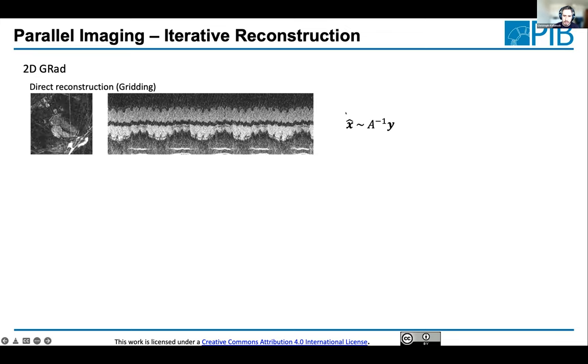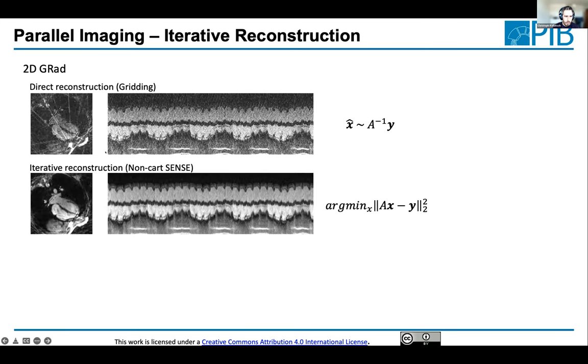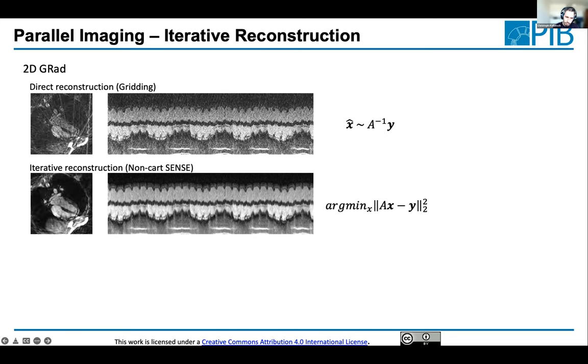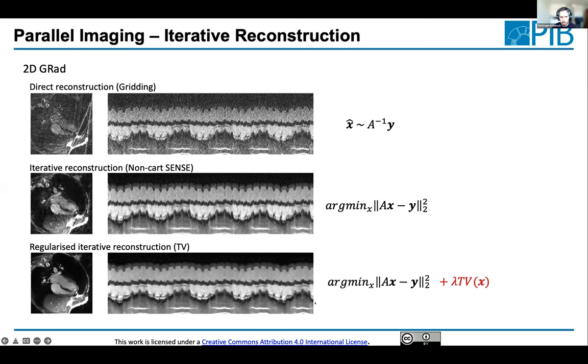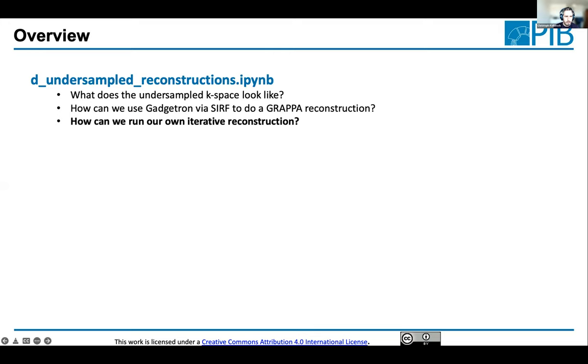This is a bit like filtered back projection. With iterative reconstruction minimizing the cost function, we can reduce streaking artifacts further. Using multiple receiver coils adds additional spatial encoding. Adding total variation regularization as a penalty further improves image quality and reduces streaking artifacts. This demonstrates how from the same raw k-space data you can get very different outcomes depending on the reconstruction algorithm chosen.